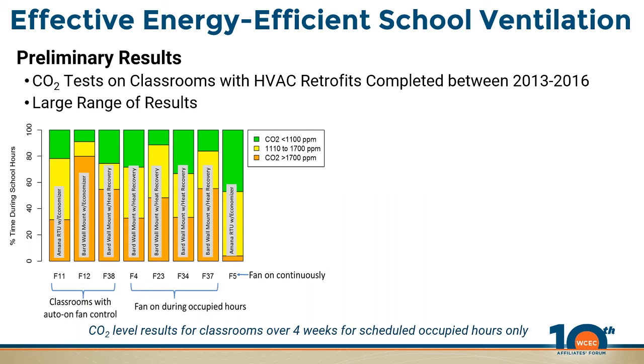So what we have here is for one particular school. Some of the classrooms were running the system with different thermostat fan settings, like you might have at home: on for the fan continuously, or oscillating with the cooling or heating. Well, these ones had auto on, which means the fan cycles with the conditioning. This one is fan on during occupied hours, and this one is fan on continuously.